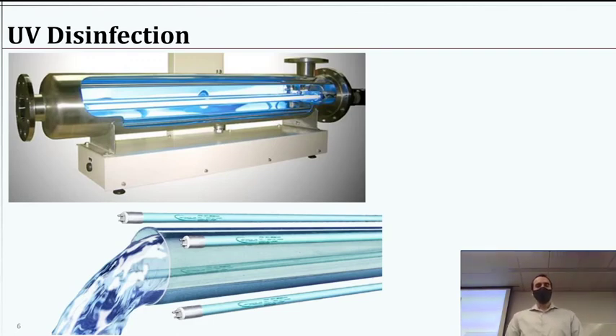So if you were to somehow scratch that off, and the glass used was allowing it to go through, then you could actually start receiving some ultraviolet light. The UV lamps, they actually have to use a fancy quartz glass to allow ultraviolet light to pass through it because normal glass will absorb it, at least most of the radiation. So if we're trying to apply it, in this case to disinfect the surfaces that we're going to work with, then we want that good transmittance. These labs, you'll see, this one has a safety glass for the cabinet that's going to protect anybody on the other side because you don't want to be looking at this because it would be very bad for your eyes, it would eventually cause blindness, and bad for your skin.